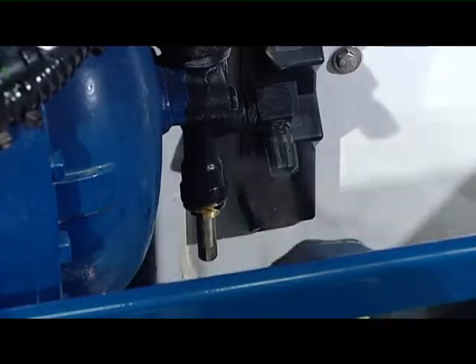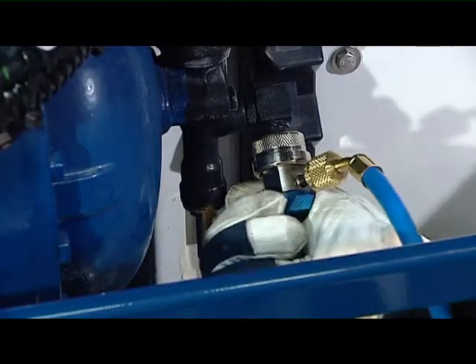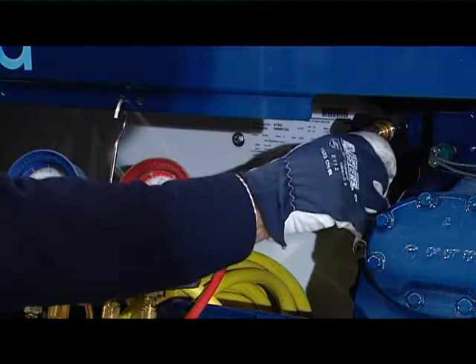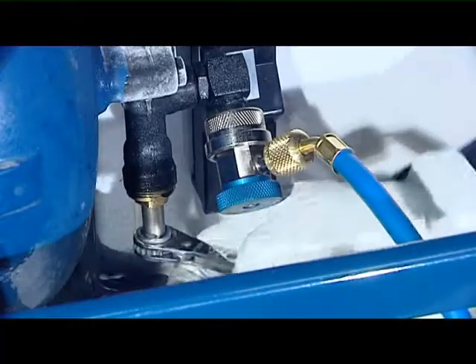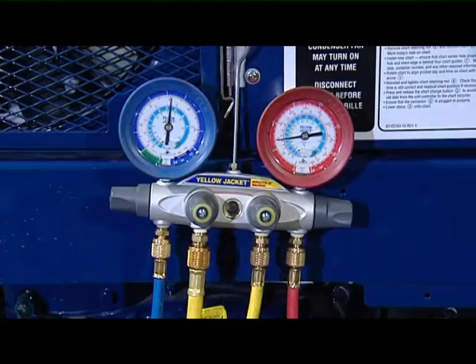Do note that for all reefer units operated by MSC, system pressures can only be viewed by connecting a manifold gauge set to the compressor. When the system is in normal operation, the service valves are back-seated. Mid-seated valve positions allow the technician to monitor system pressures. Front-seated position isolates the compressor from the system.